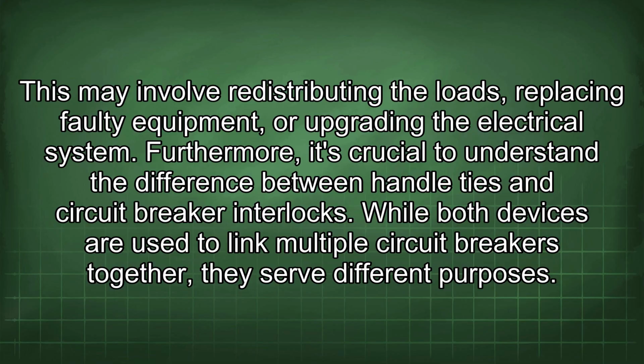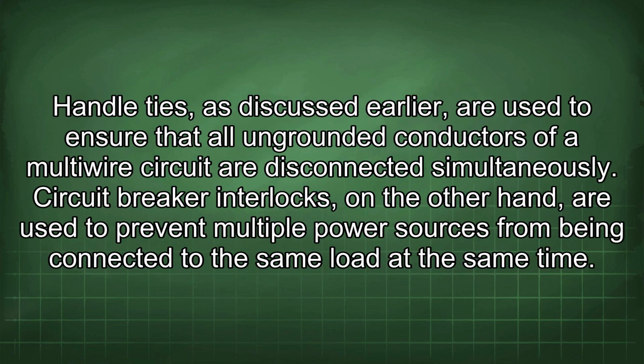Furthermore, it's crucial to understand the difference between handle ties and circuit breaker interlocks. While both devices are used to link multiple circuit breakers together, they serve different purposes. Handle ties, as discussed earlier, are used to ensure that all ungrounded conductors of a multi-wire circuit are disconnected simultaneously. Circuit breaker interlocks, on the other hand, are used to prevent multiple power sources from being connected to the same load at the same time.